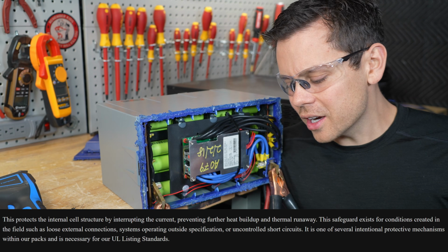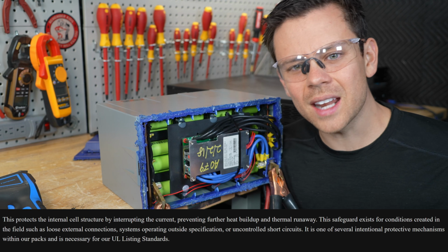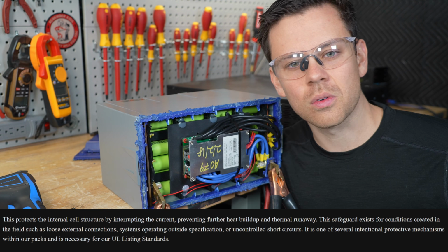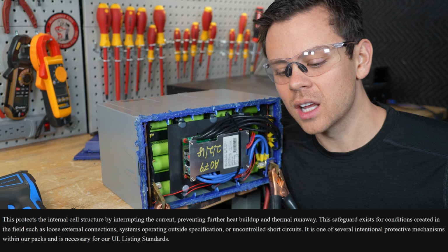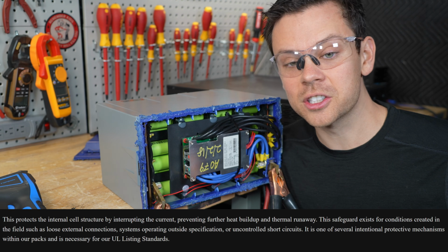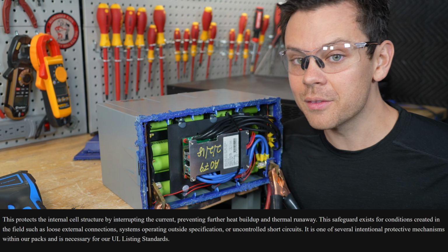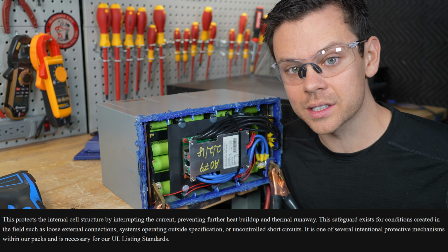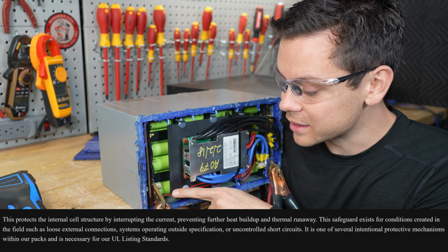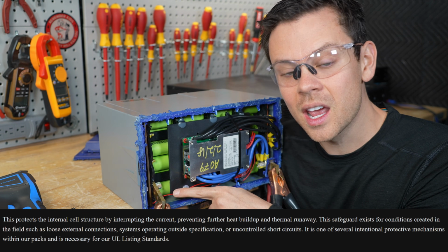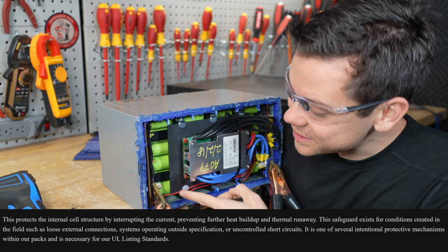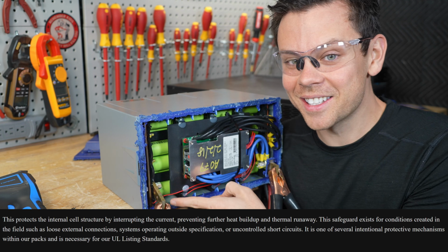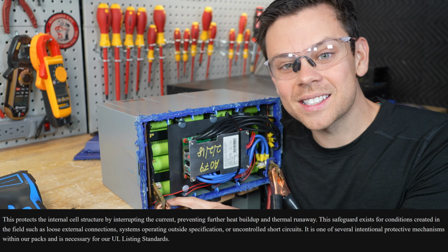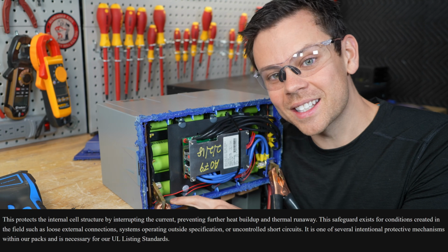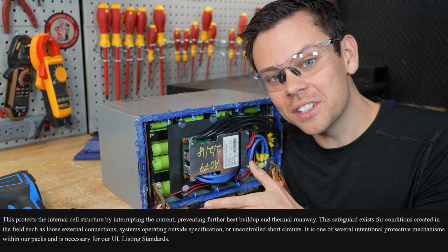And the final one is uncontrolled short circuits. What does that actually mean? Uncontrolled—if you have a short circuit, you need to have a protection device because you're not there to control it. You need a fuse or circuit breaker that's UL listed. If a laboratory is passing this as an overcurrent protection device, they need to be investigated. This is not disconnecting. It is not. And if this is the last safety mechanism and it's not disconnecting, then this is not a safety feature.